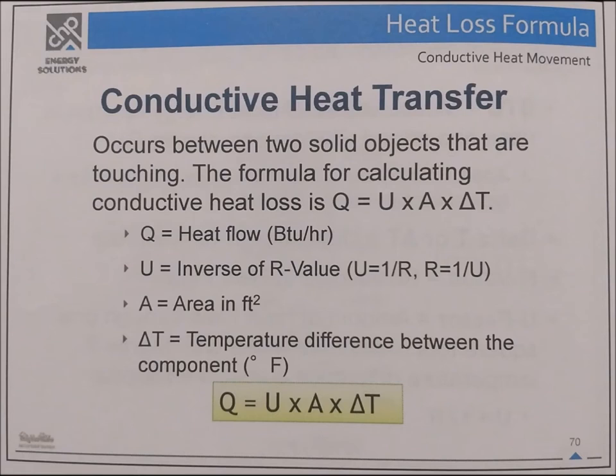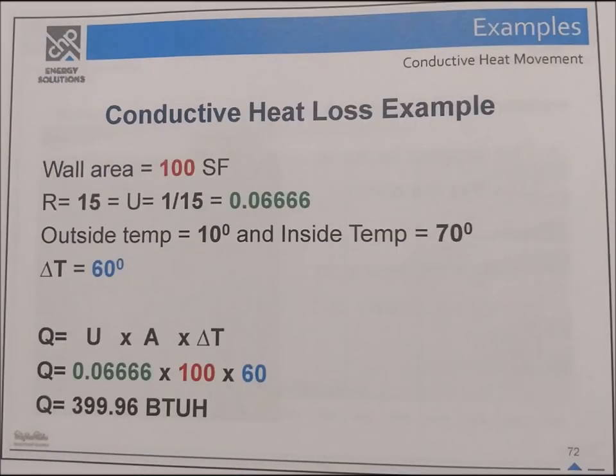A is the area in square feet and delta T is the temperature difference in degrees Fahrenheit. So the formula is Q equals U times A times delta T. Conductive heat loss example: Wall area equals 100 square feet; R equals 15, so U equals 1 divided by 15 equals 0.0667. Outside temperature is 10°F, inside is 70°F, so delta T equals 60°F. Q equals 0.0667 times 100 times 60 equals 399.96 BTUH.